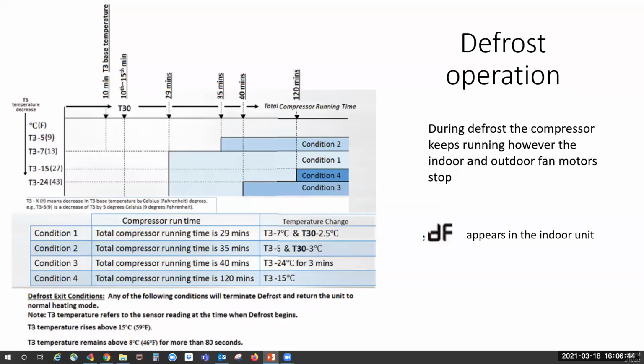When going into defrost, the compressor will continue to run. The indoor and outdoor fans will shut down. Defrost can last up to 10 minutes. And like I said, on some of them that do have displays, there'll be a DF on the indoor unit. So this would tell us.